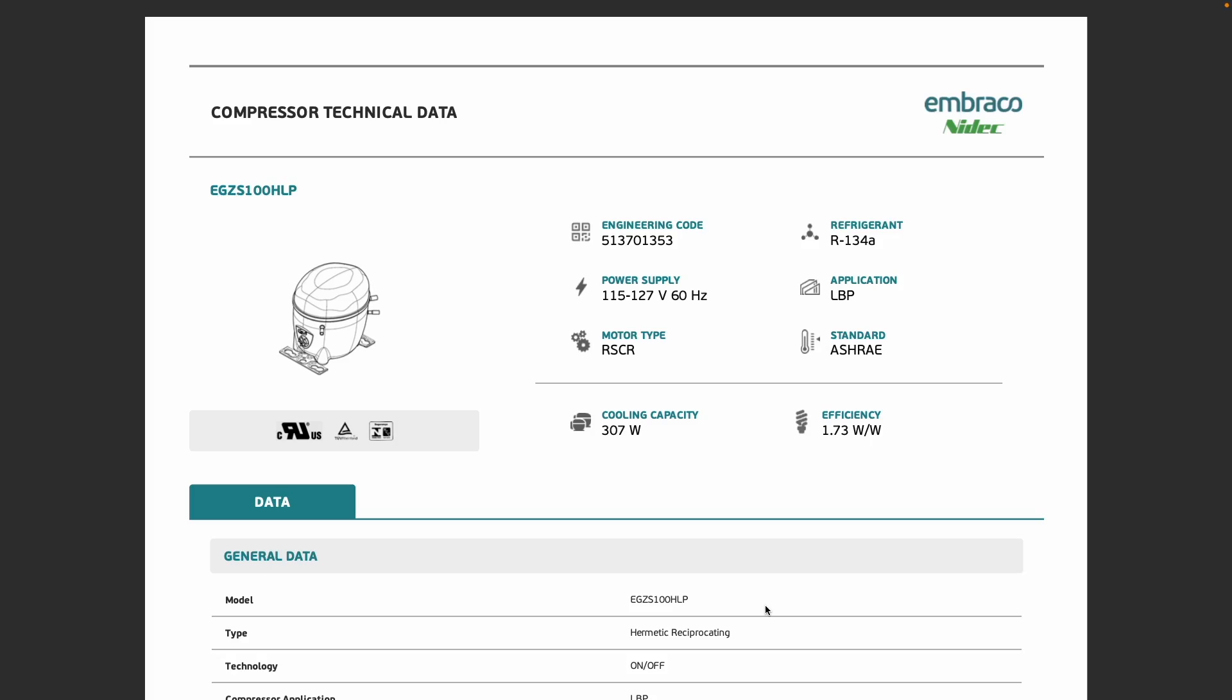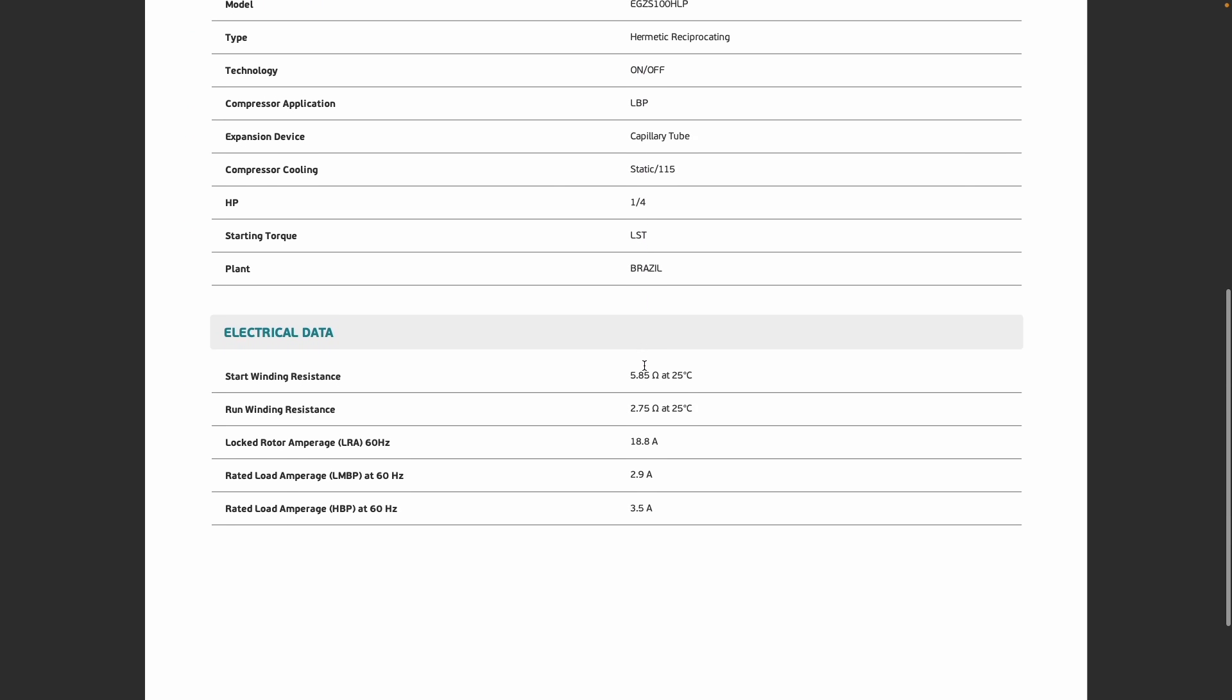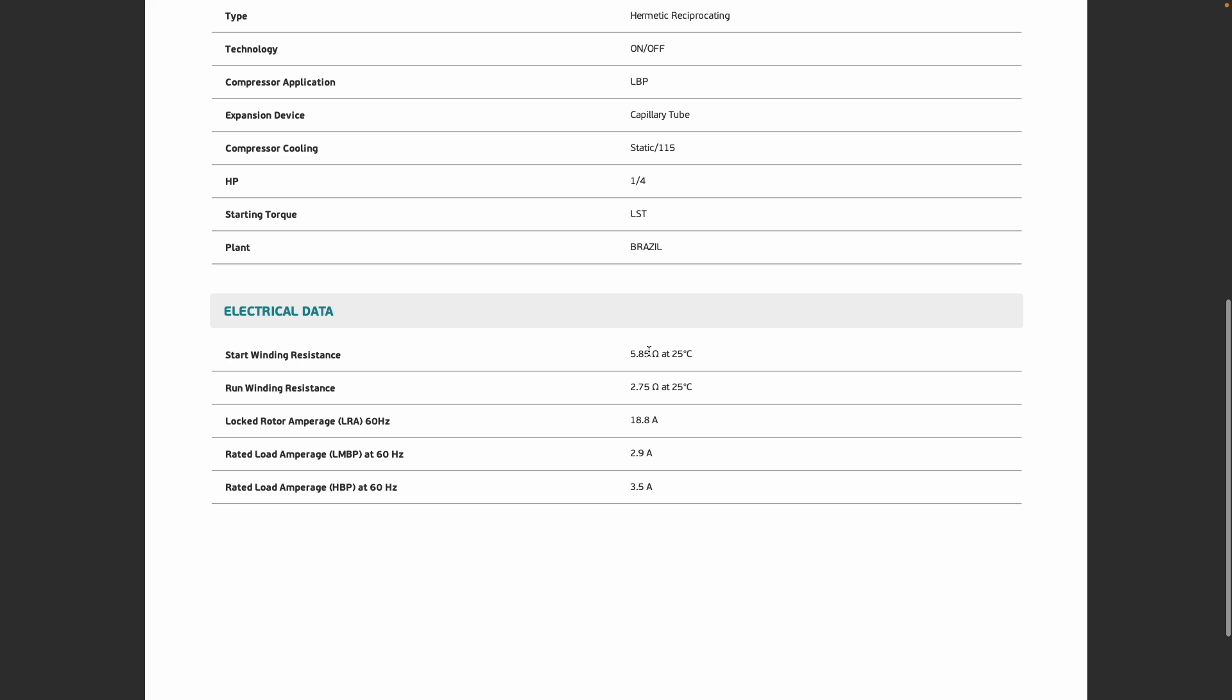I've pulled up the technical data for this compressor. There's lots to look at but I'm only interested in two pieces of information. First, the motor type - we have an RSCR motor which stands for resistance start capacitor run. In addition, I want to know about the windings in this compressor. In residential fridges with single phase compressors you'll have two windings: start and run. I want to know the resistance across those windings. The start winding resistance should be about 5.85 ohms and the run winding should be about 2.75 ohms.